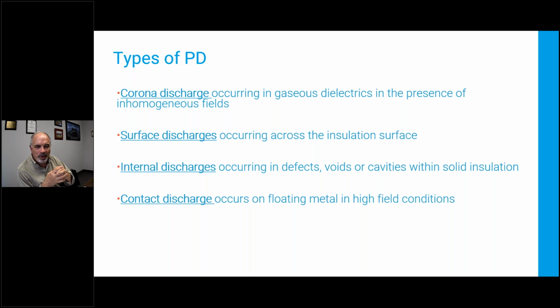Internal discharge is where we have something totally within solid insulation. It could be an air bubble inside molded insulation. It could be some sort of cavity. It could be a crack inside the insulation. It could be a gap left in the termination of a cable that was done by an unskilled joiner, those sort of things. This is harder to detect. It creates various different characteristics than surface discharge. It's harder to correct. It's also slower moving, and I'll talk about why. So they're different.